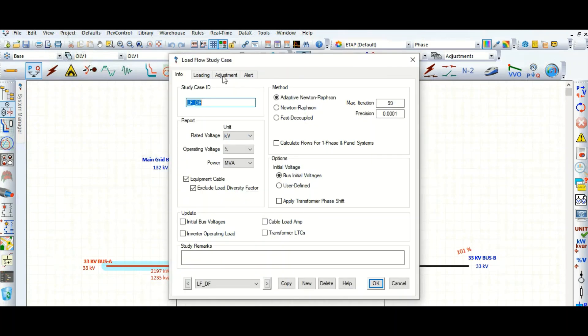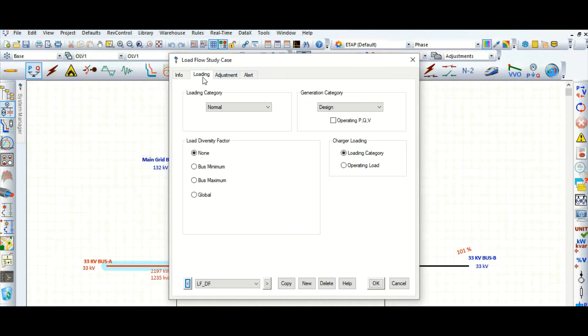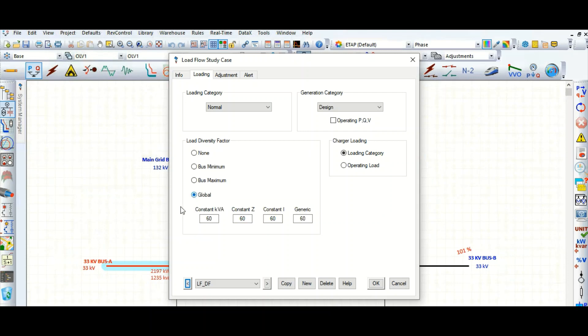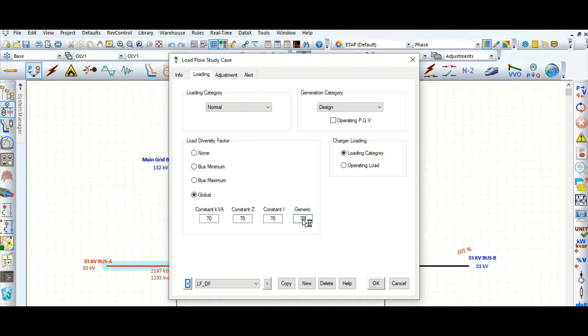I have got some site data, so based on that I will apply the global load diversity factor. Let's apply here. From site I have got that 70 percent loading we need to consider, so change this to 70 percent. It will apply globally, that means it will apply for all the switchboards connected with this power system network at all voltage levels: 132 kV, 33 kV, 6.6 kV or downstream.